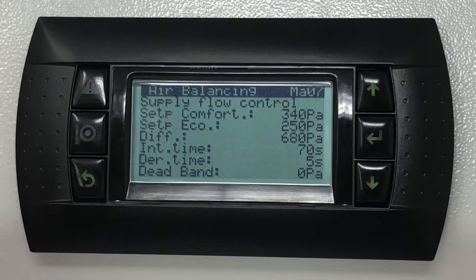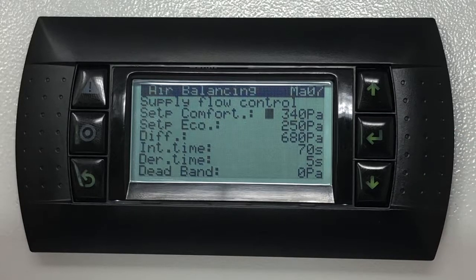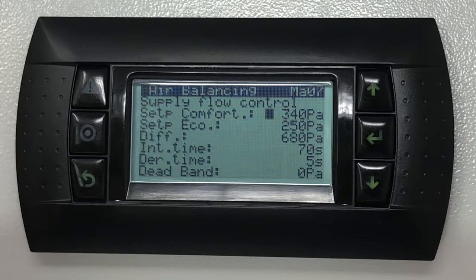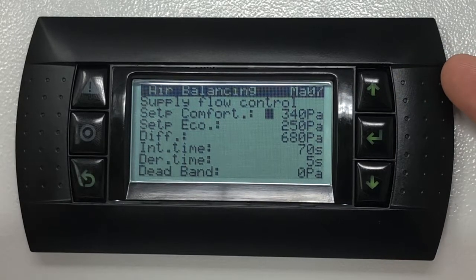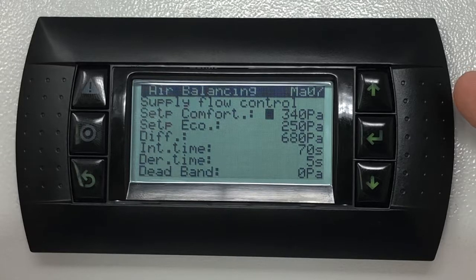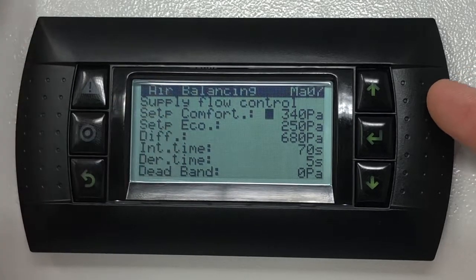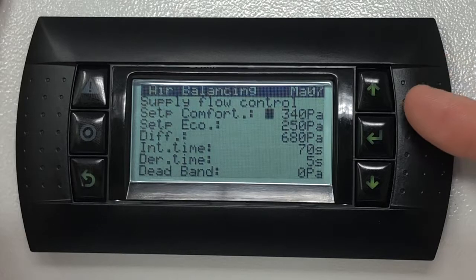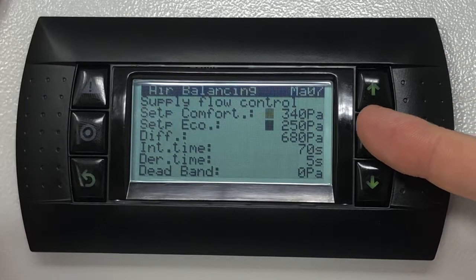By pressing the enter key the cursor will move to the next field in line. The set point in comfort mode is the target set point that the controller will aim to maintain on the supply section. If the software has been set to operate both in comfort and economy modes, in this screen you'll be prompted with a supply fan speed set point also for the economy mode.